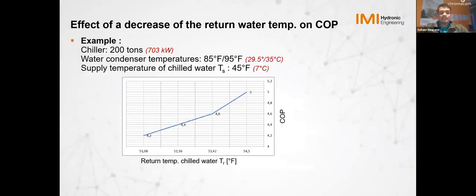So when we look at a chiller, this is a simulation which was done for a 200-ton chiller with 85-degree and 95-degree condenser temperature and a supply temperature of 45 degrees. So when you look at this chart here, if the return temperature was set at 54.5, we had a coefficient of performance. I mean, we want a higher coefficient of performance for our chiller to be more efficient.